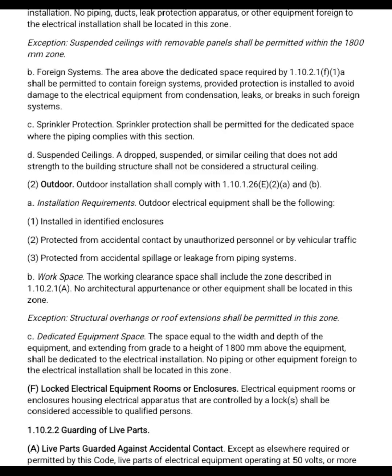This indicates the rules for indoor and outdoor. The indoor rules are: nothing should be placed above electrical equipment unless it is allowed and properly protected from leaks or damage. Second, sprinkler pipes are allowed only if they follow safety rules. Third, drop or suspended ceilings do not count as structural ceilings. Outdoor rules are: outdoor electrical equipment must be placed inside a proper enclosure, be protected from accidental contact by people or vehicles, and be protected from leaks or spills from pipes. Rooms with electrical equipment must stay locked and only qualified persons can enter. And live electrical parts must be guarded or protected so people cannot accidentally touch energized components.